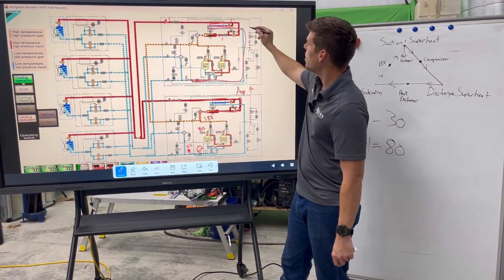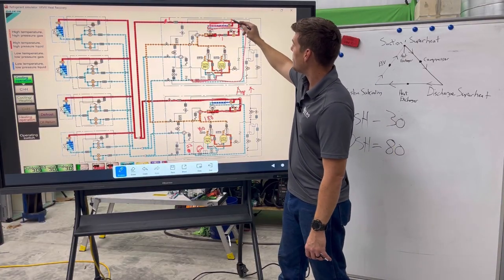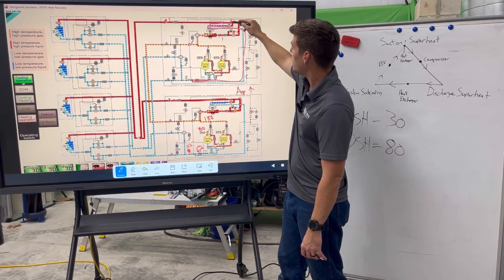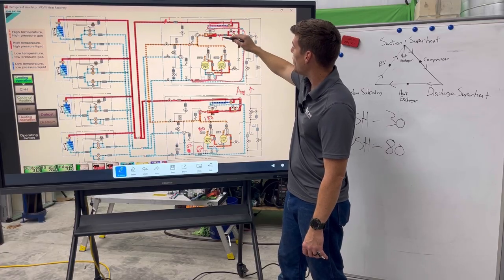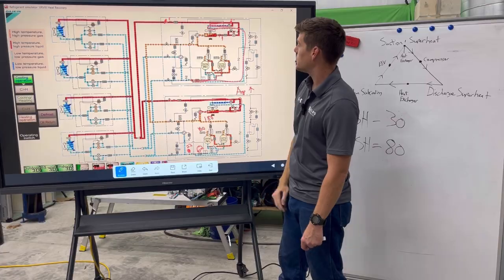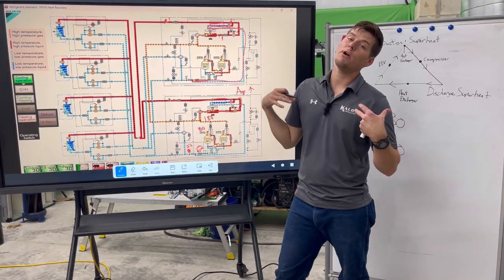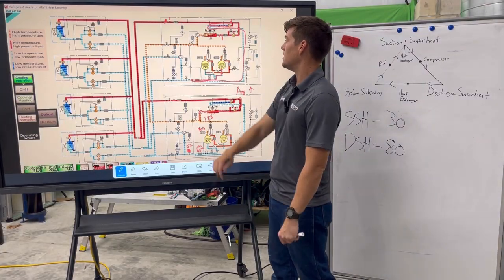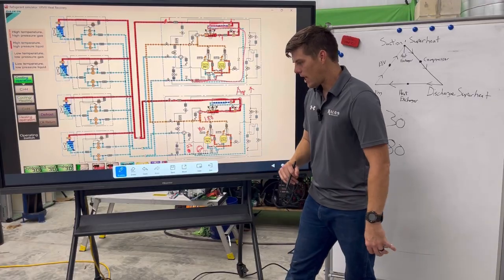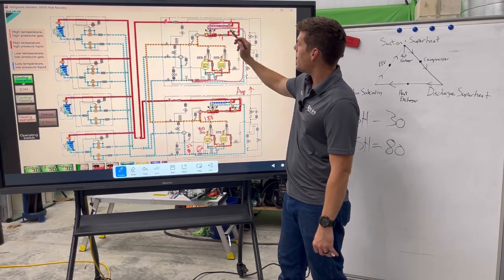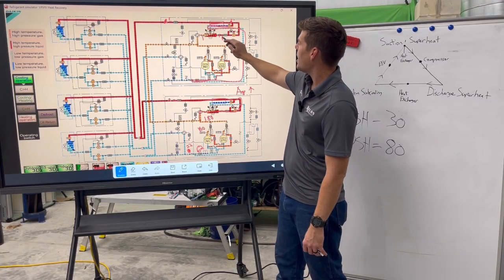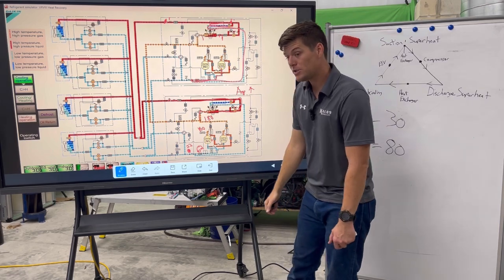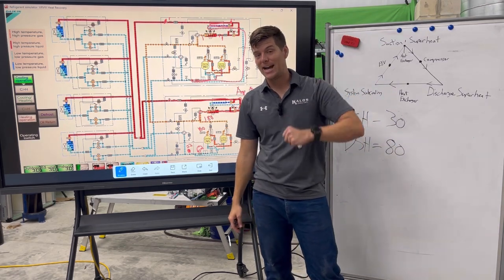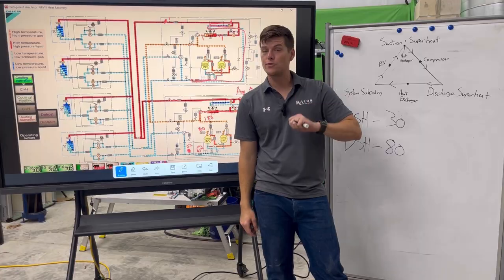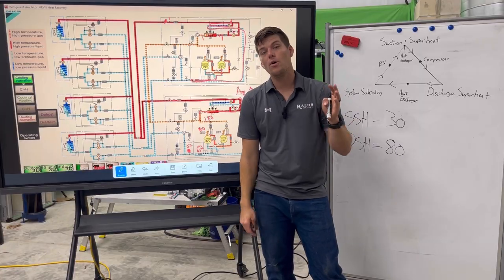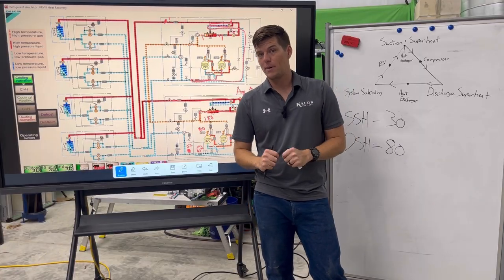And so for here, we have a few choices. We can either measure here, right, that sensor there, or we can measure right before the expansion valve leaving our heat exchanger. Now me, personal preference, I like to measure it right as it's leaving the heat exchanger. Why would I do that? Well, I want to do that because I want a true accurate measurement, one, before and also after. Why are there 2 sensors here? Well, those 2 sensors, one is a de-icer, which is used for defrost, only defrost, and the other one is my actual liquid temperature for my heat exchanger.